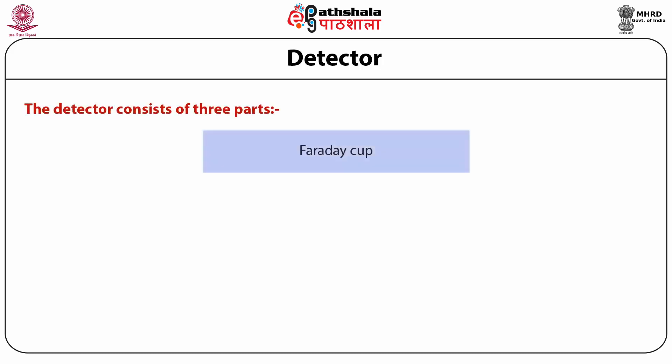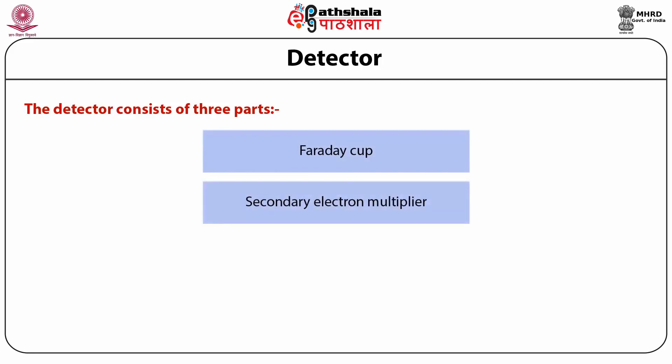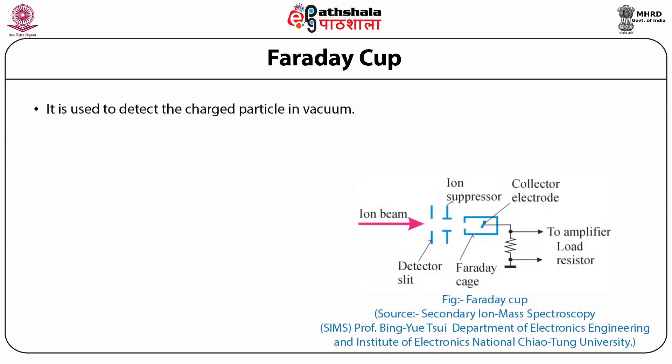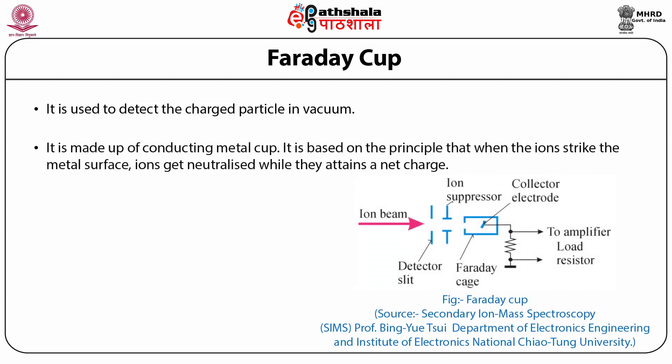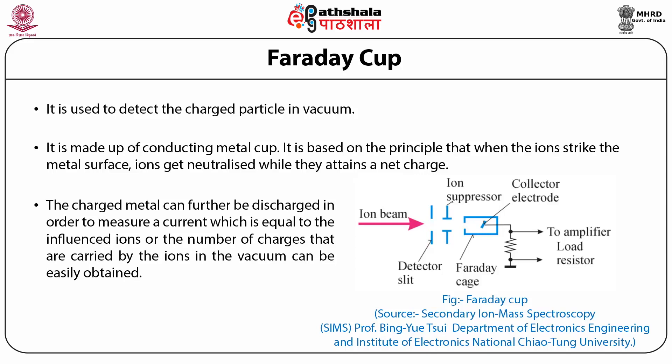The third important component is the Detector, which consists of three parts: Faraday Cup, Secondary Electron Multiplier, and Micro Channel Plate. The Faraday Cup is used to detect charged particles in vacuum. It is made of a conducting metal cup and is based on the principle that when ions strike the metal surface, they get neutralized while attaining a net charge. The charged metal can be discharged to measure a current equivalent to the incident ions, and the number of charges carried by ions in the vacuum can be easily obtained.